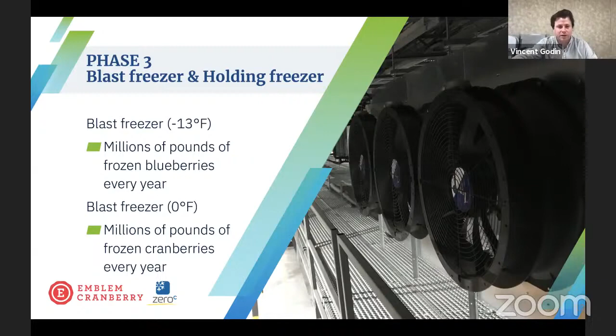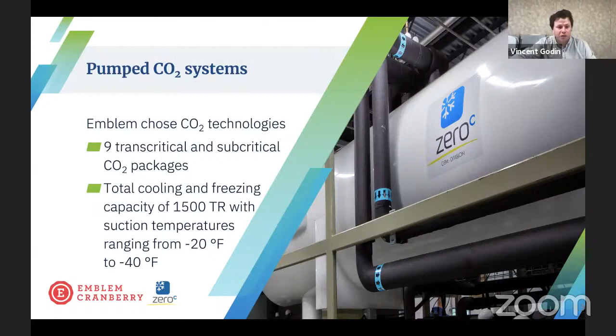So all of our systems include a pumped CO2 technology. So we have 9 transcritical and subcritical CO2 racks or packages. And the total cooling and freezing capacity is around 1,500 tons of refrigeration with suction temperatures ranging from -20 to -40 F, depending on whether it is for cranberries or for blueberries. The difference in temperature at which we want to hold the cranberries or the blueberries depends on the fact that blueberries will be held at a lower temperature of -13 F because they have more sugar content that will cause them to leak if they're not held cold enough.